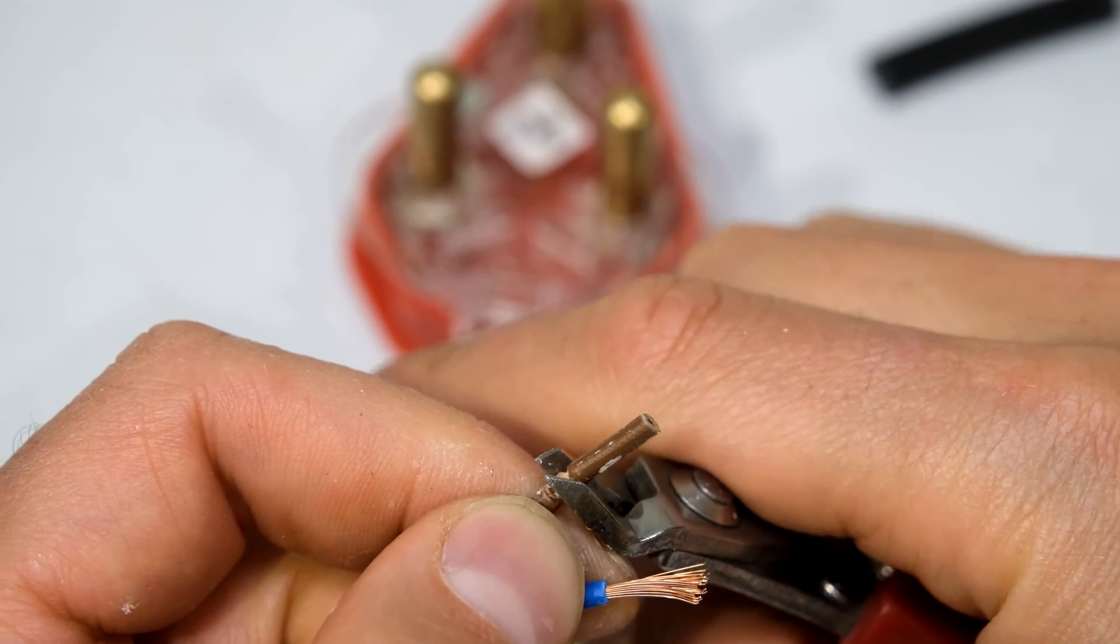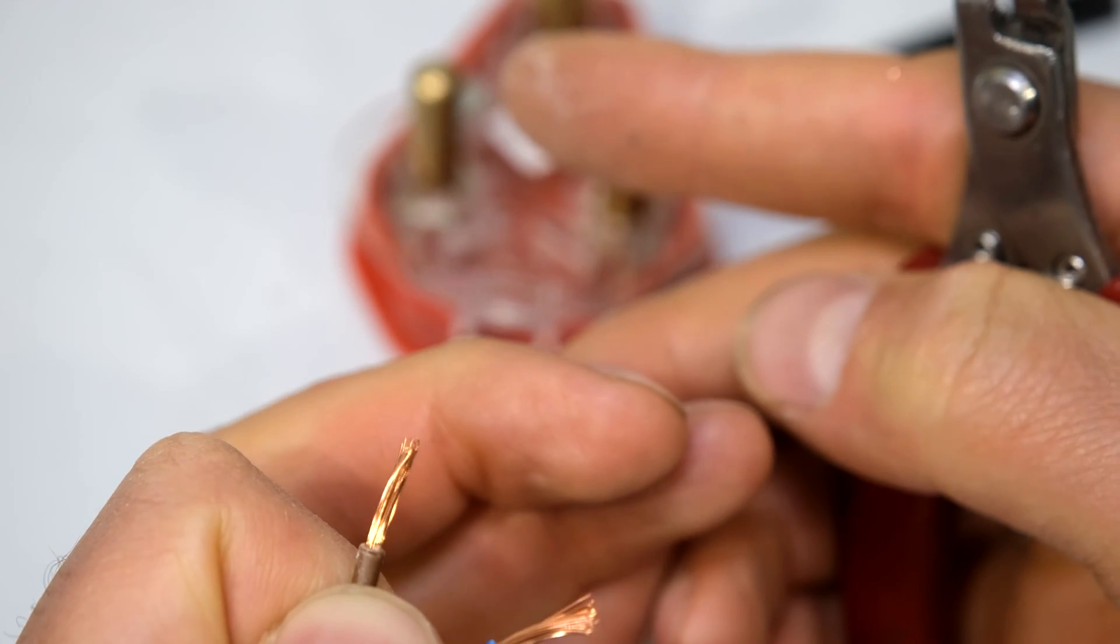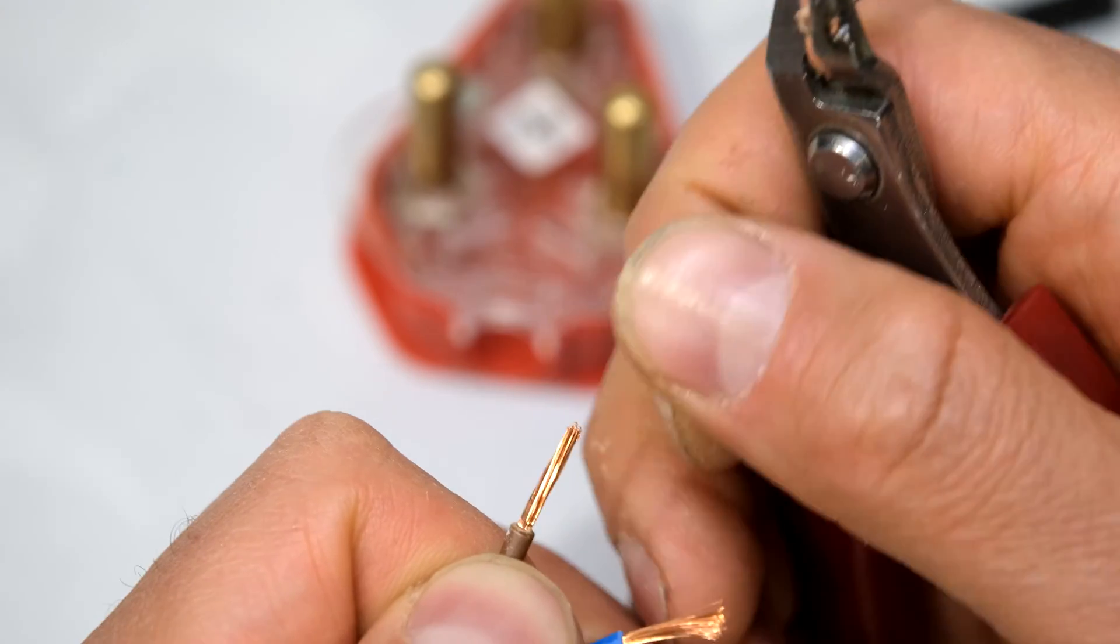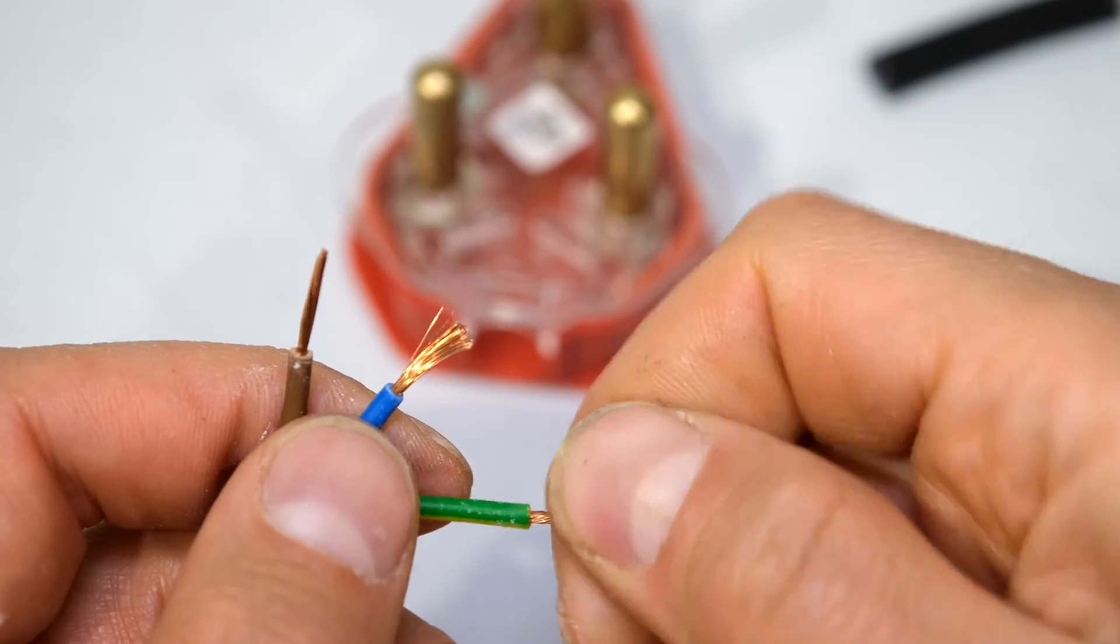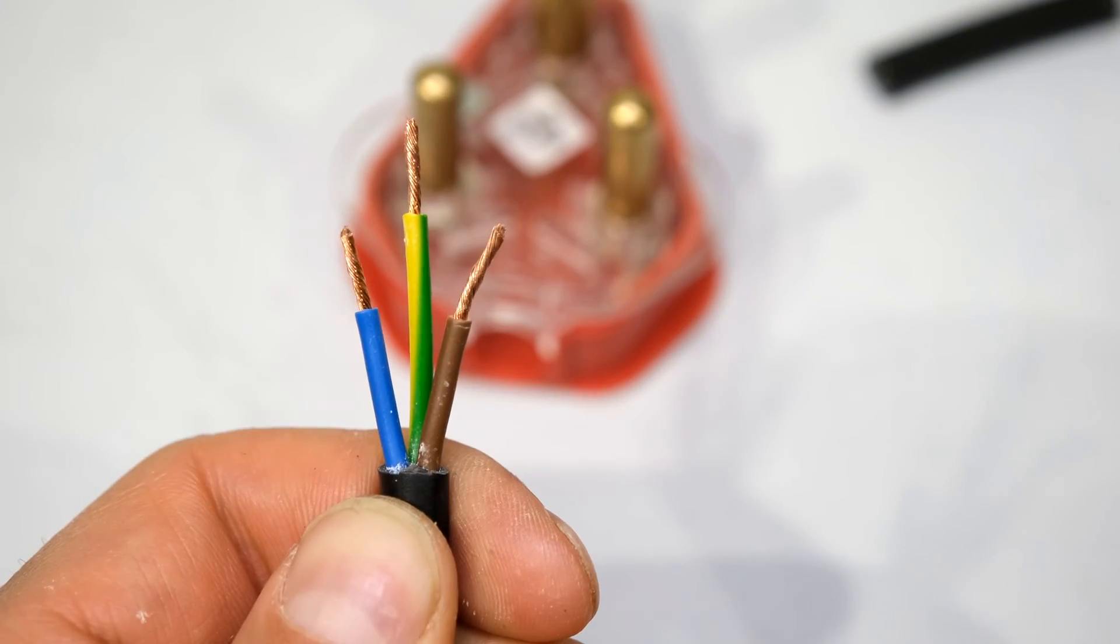Now I remove the insulation of the neutral and the live wire. Please note, I do not cut through the insulation. What I do is it's more of a pulling function and a tearing. As you can see, I tear the insulation away and this way I haven't damaged any of the copper strands. Make sure you twist the copper strands. Your wire should now look like that.